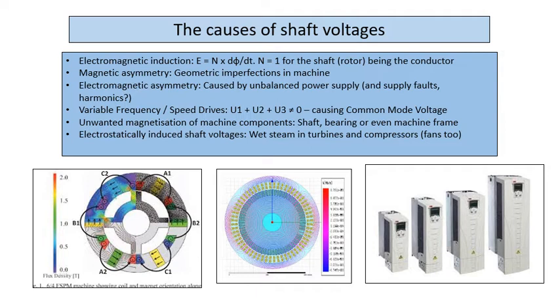VSDs, Stian's mentioned this. Then also unwanted magnetization of machine components. I say unwanted because of course you've got lots of magnetic fields in a machine. Your unwanted locations are typically on a bearing housing, your shaft near the journals, areas like that. And then also electrostatically induced shaft voltages. Wet steam in turbines and compressors, and interestingly enough, the VSD application that I measured was a fan, and we measured tremendous shaft voltage, way more than from the VSD, just when the driven load was connected.